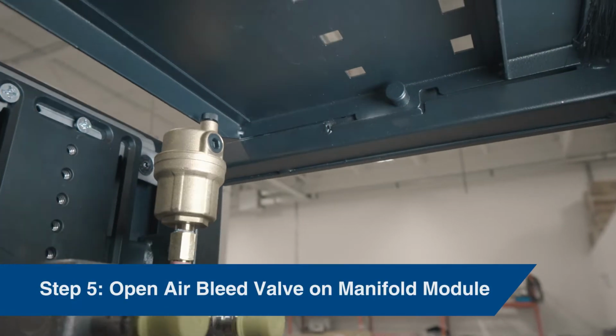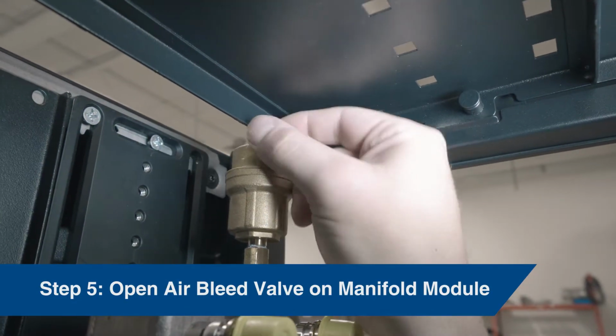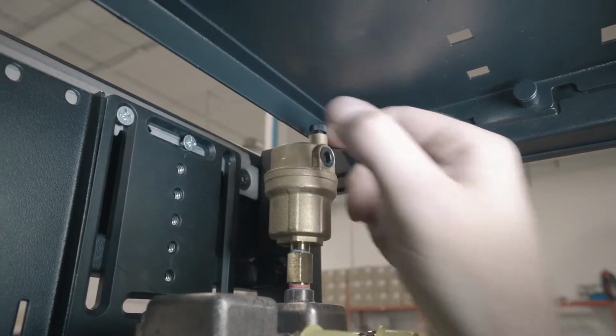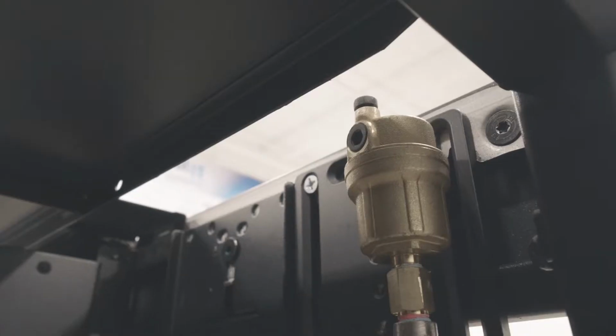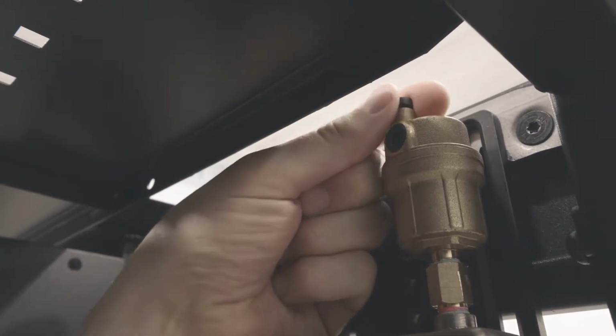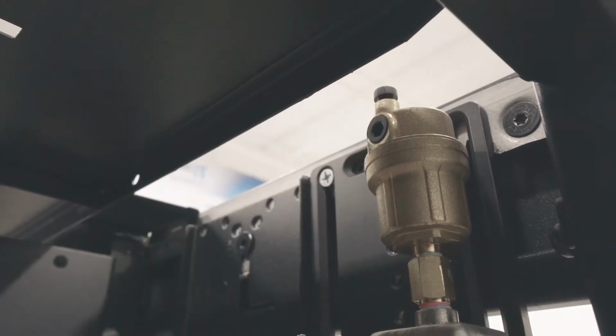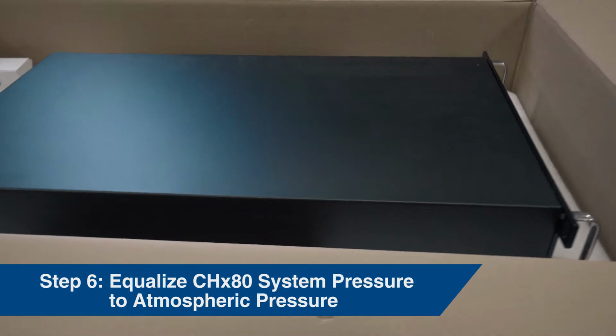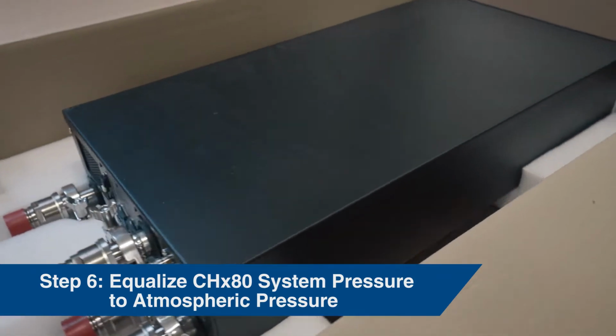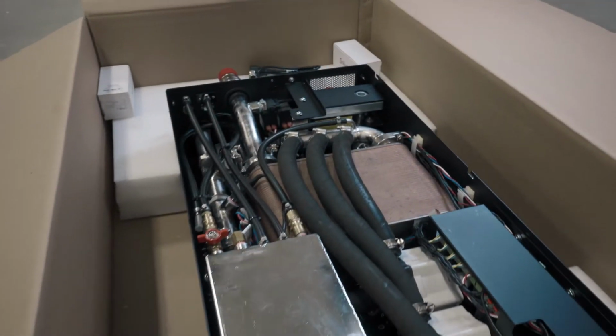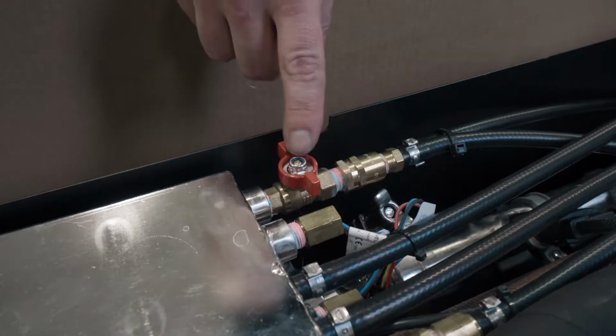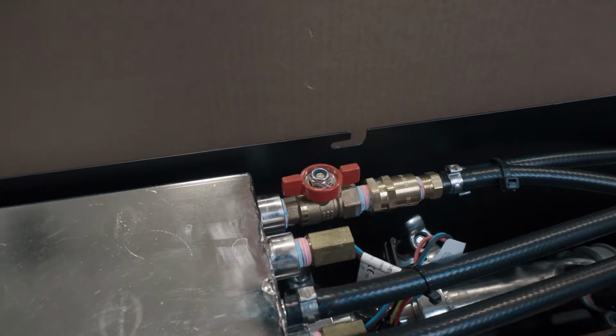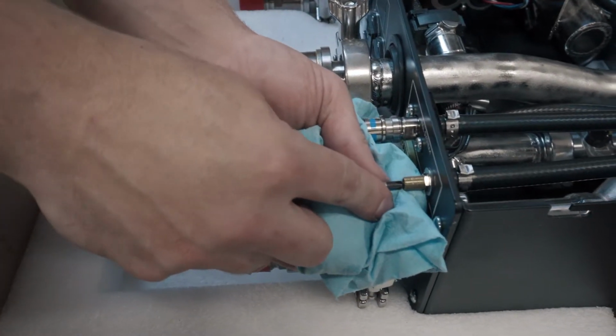Step 5. Open air bleed valve on manifold module. Locate the automatic air bleed valve on top of the manifolds. Open the valves to relieve pressure from shipping. Leave them open. Step 6. Equalize CHX80 system pressure to atmospheric pressure. Before removing the heat exchanger from the crate, open the overpressure ball valve and then depress the Schrader valve to vent any excess pressure that may have built up in transit.